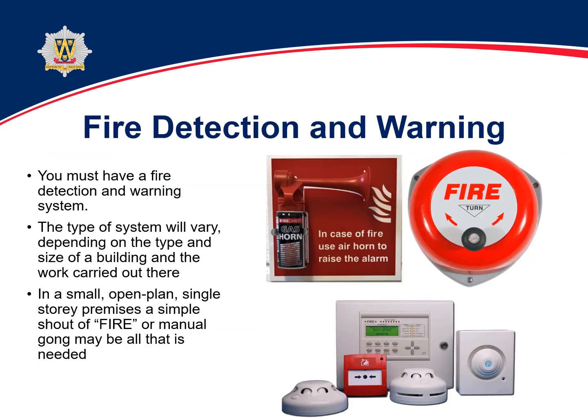Okay, fire detection and warning then. So by far the best detector of a fire is the human eye. So you must have some form of detecting a fire and giving warning that a fire has started. And this will depend on the size of your premises and the work that's carried out. So small open plan single story, a shout of fire might work. Larger, more complex premises may need automatic fire detection.